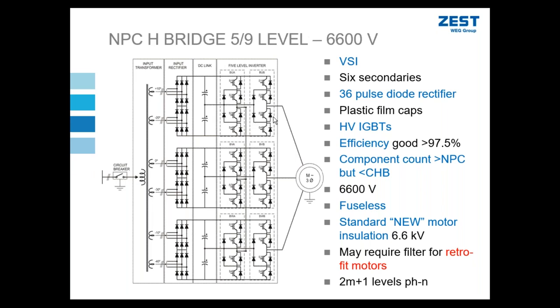I've got six power arms compared to 18. So there is arguably less reason to put in bypass and redundancy on this topology. But you know, it's got a couple of disadvantages. It's not as motor friendly, with the output being 5 level phase to neutral and 9 level, compared to the 6.6 kV, which is 13 level and 25 level phase to neutral and phase to phase. So it's a lot of give and take.